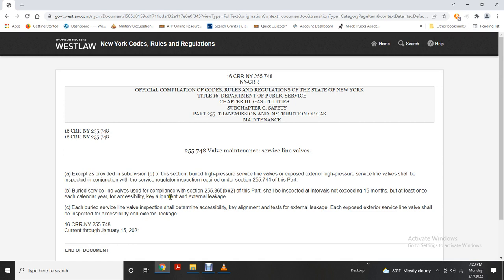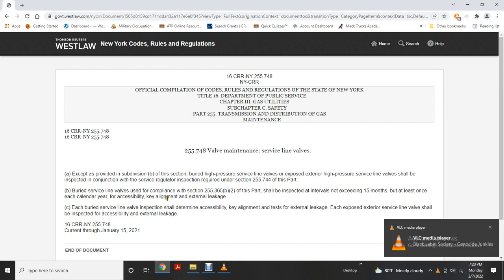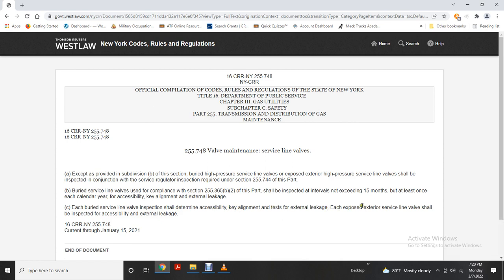Buried service line valves, compliant with 255-365B2 of this part, shall be inspected at intervals not exceeding 15 months, but at least once each calendar year for accessibility, key alignment and external leakage. Each buried surface line valve inspection shall determine accessibility, key alignment, to test and allow for external leakage when exposed. Each exposed exterior service line valve shall be inspected for accessibility and external leakage.